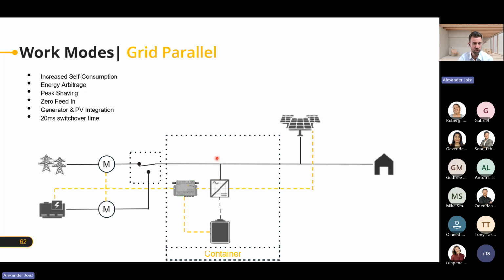Now if we put a switching element at the front, it could be an STS or anything, with a 20 millisecond switchover time. We could add this to switch between grid and generator, or just to switch off the grid from it without a generator, that doesn't matter. So now we have a full backup system in this case, but we're still working in grid parallel, so this is pretty easy.